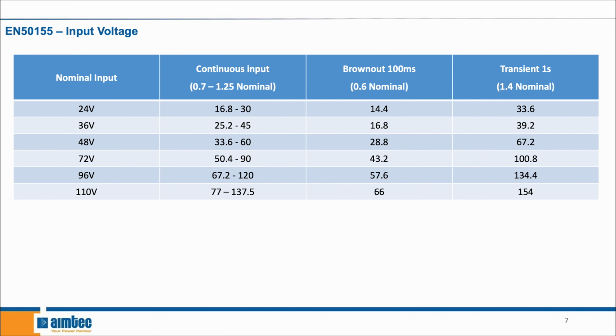So to begin, we're going to look at the input voltage. The auxiliary power drives multiple plug doors, motors, and relay coils. Since there are a number of heavy loads connected to the auxiliary power, the voltage is expected to fluctuate. The table shown here shows the EN 50155 requirements on input voltage. Railway electronics need to accept wide input voltage ranges of 0.7 to 1.25 times the nominal voltage.